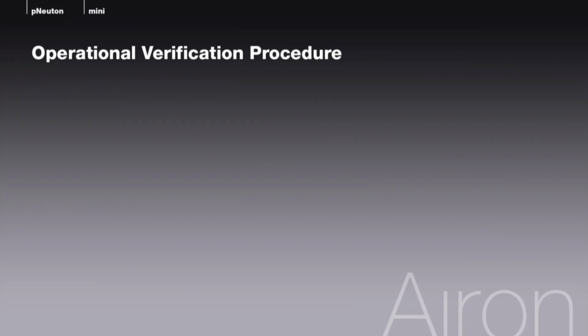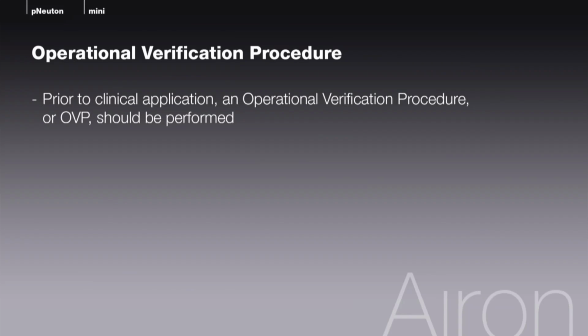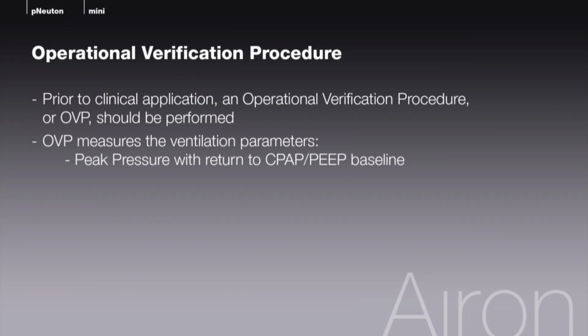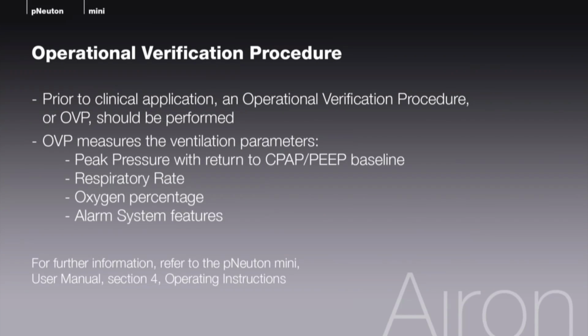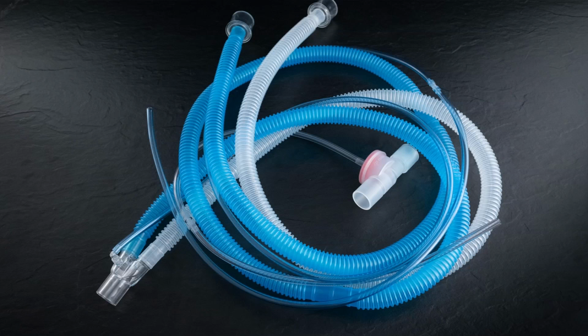The operational verification will measure the ventilation parameters, peak pressure with return to CPAP PEEP baseline, respiratory rate, oxygen percentage, and the alarm system features. For further information, please refer to the User Manual, Section 4, Operating Instructions. Now let's turn our attention to the pNeuton mini's circuits.